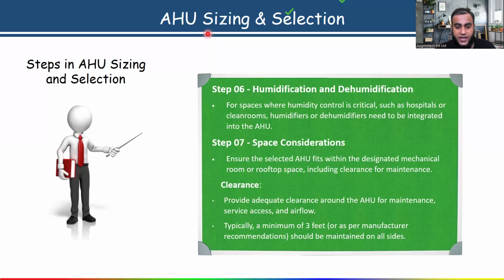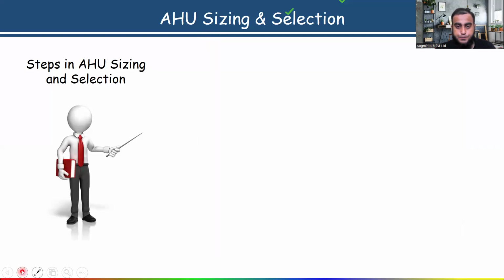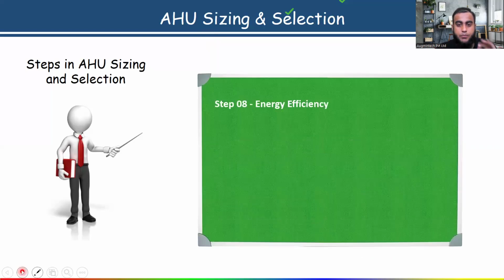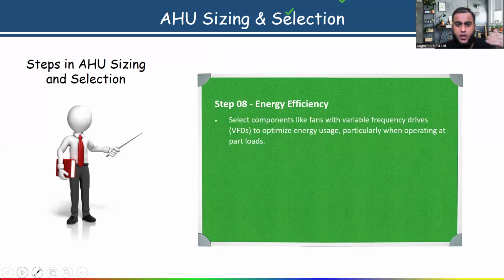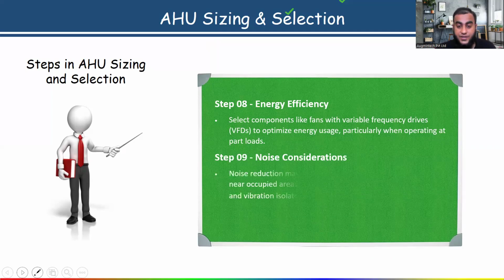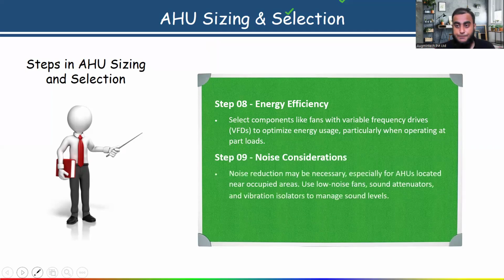Now let's see the next point which we have to discuss. Step number 8, energy efficiency. It means that we have to select components like the fan for energy efficiency. The fan inside the AHU should be used with a variable frequency drive, VFD, to optimize energy usage, particularly when operating at part load. Okay, then the next step is noise consideration. How much noise do we have to maintain?